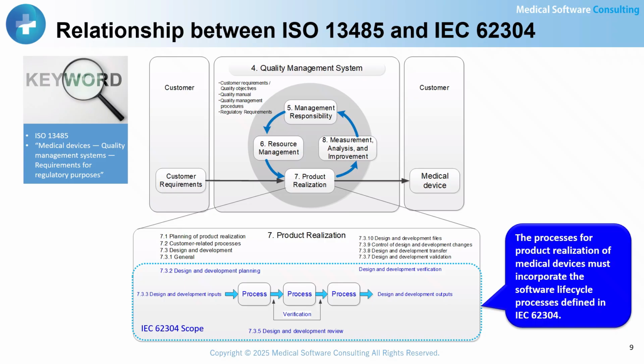It is specifically designed for medical devices and therefore cannot be used as a substitute for ISO 9001. ISO 13485 focuses on ensuring consistent quality across the entire life cycle of a medical device, from design and development through manufacturing and ultimately to disposal, so that patient safety is maintained. It outlines the requirements for establishing a quality management system that demonstrates an organization's capability to consistently deliver safe medical devices and related services while meeting both customer and regulatory requirements.